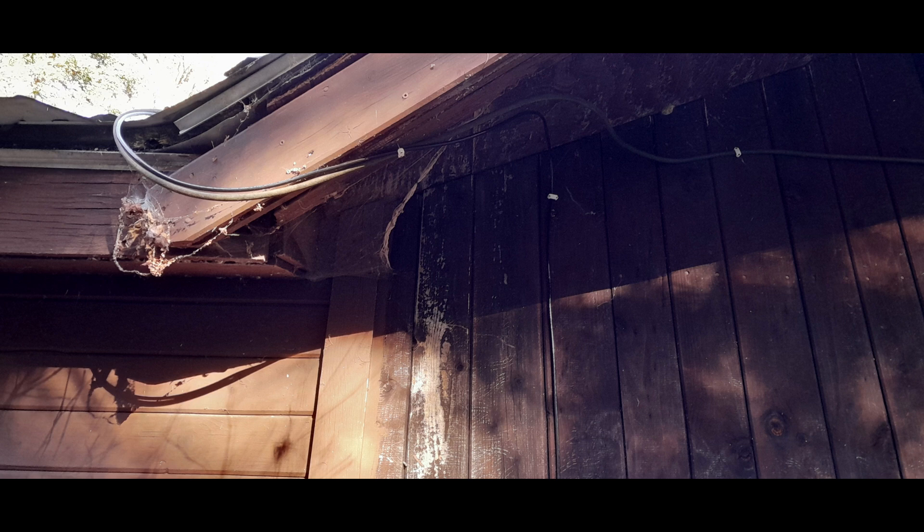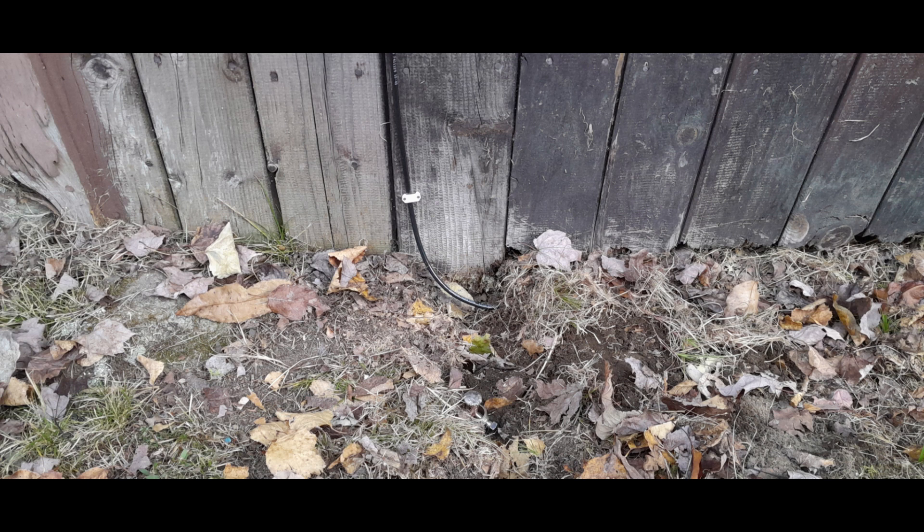Looking up from the valley where the CB and ground wire ran, I brought the cables down and put a drip loop, giving enough slack so they wouldn't pull against that metal roof. I ran them up underneath the eaves, split the ground wire off, and ran it down the wall. Thankfully we were able to drive that eight-foot ground rod by hand because the hammer drill accessory I had wasn't the right size. My brother encouraged me to try it by hand — both of us working together, one stabilizing the rod and the other swinging the hammer, swapping off as we got tired. We got the ground rod connected and drove the connection just beneath the soil so weed trimmers and lawnmowers wouldn't hit it, then tucked the wire into a small hand-dug trench to protect it and eliminate a trip hazard.